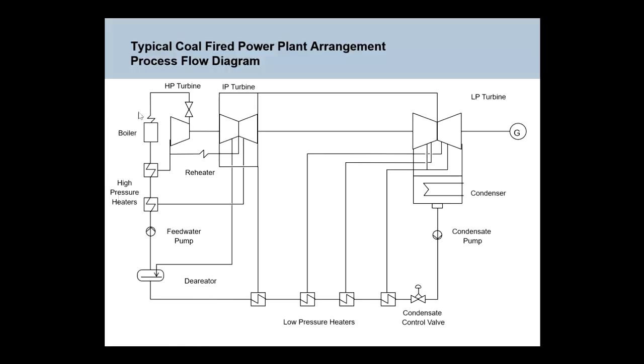Okay? So I'm producing superheated steam that goes through some valves into my HP turbine where it's expanded, comes out lower pressure and somewhat cooler. It goes back into the boiler and is reheated, comes into an IP turbine where it expands typically in two ways, comes out of the IP turbine across to an LP turbine, expands again, and then drops out of the bottom of the LP turbine into a condenser. Condenser is a very large box, I guess you call it, which has thousands of tubes going through it with cooling water through them. The idea of the condenser is to cool that steam that's been ejected from the LP turbine into water, which is then collected through a pump, pumped around this cycle. It's pre-warmed again through a deaerator.